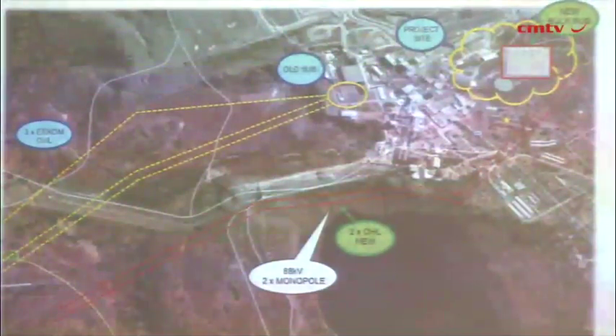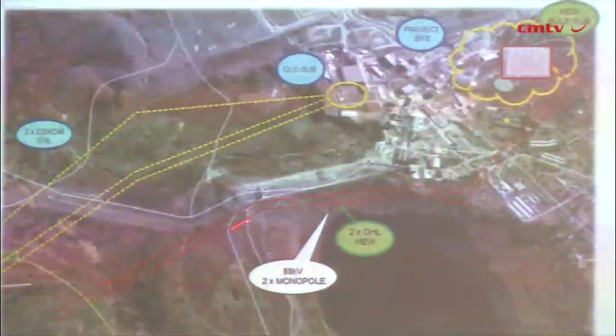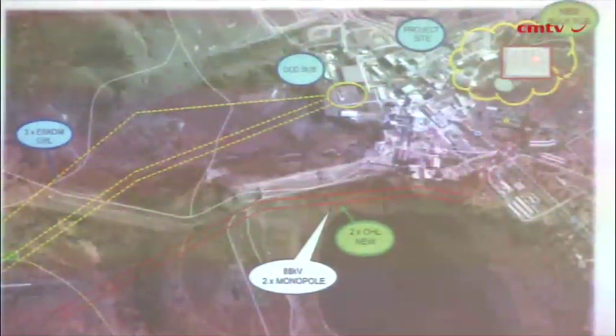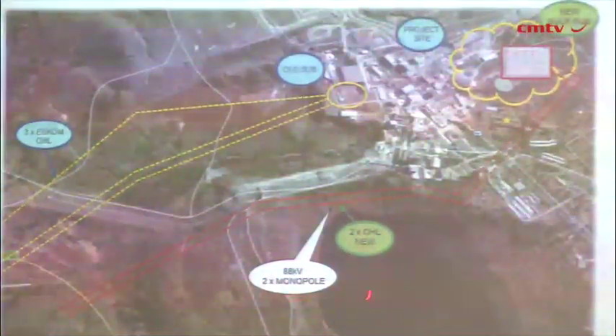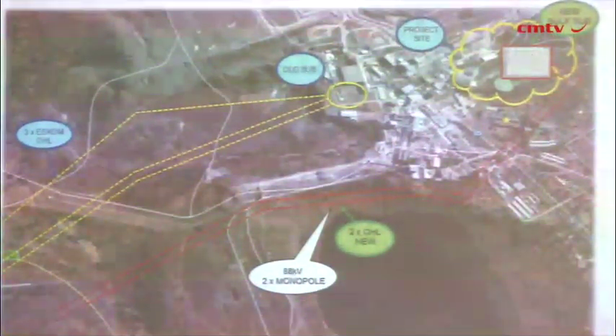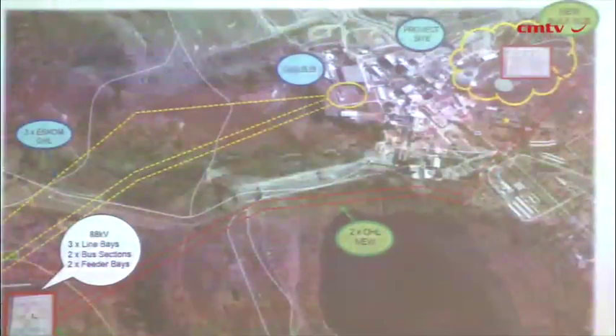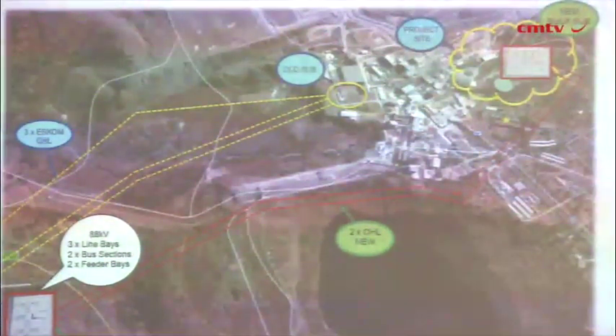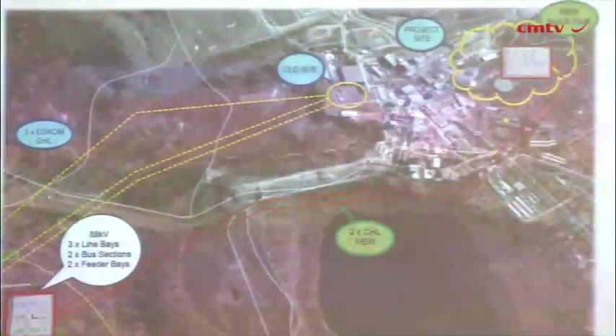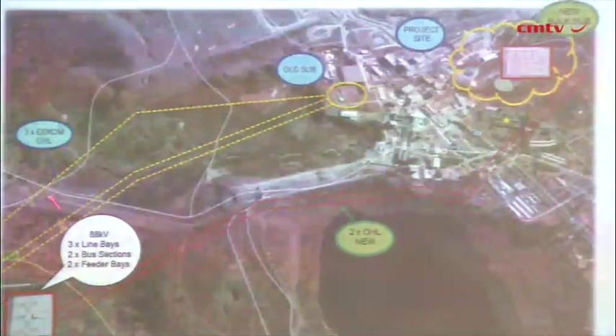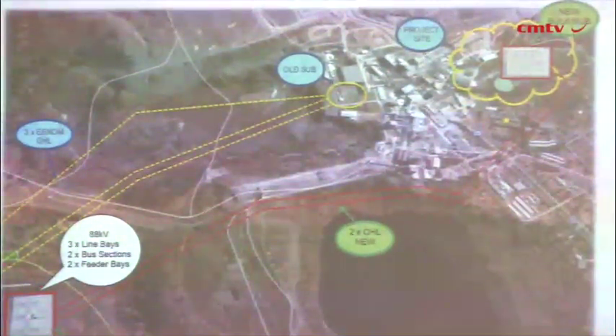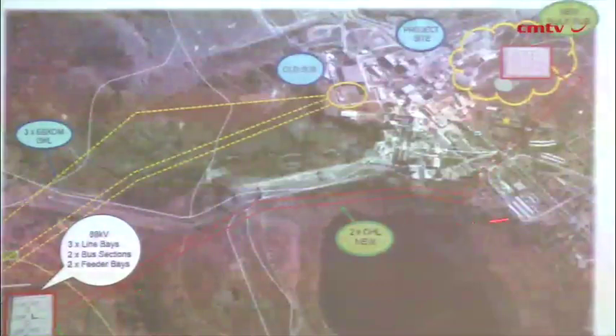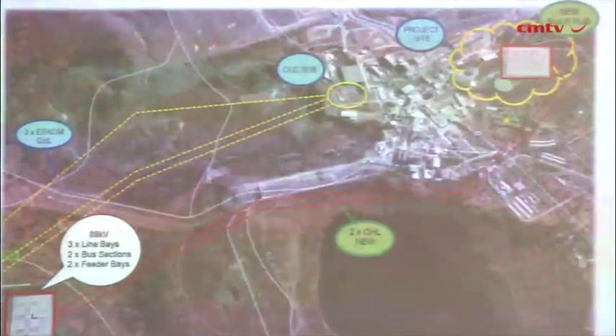We then had to design and construct a dual circuit 88 kV overhead line, which we did with monopoles. This was connected to an 88 kV Eskom self-built switching type station, where the 3 existing lines were diverted through the switching station to allow energy to flow directly into the mine's property.